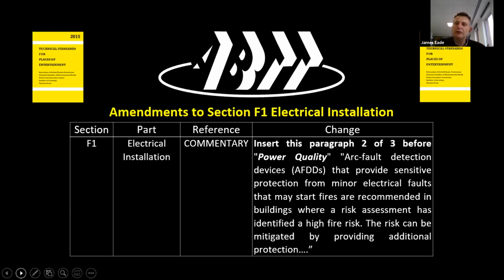But if the risk in a particular environment is low, like an event, for example, it's a managed system. Everyone's there while it's on, you turn it off when you go home at night. So if there are any latent faults that an AFDD would detect, they'll be detected anyway, because you'll see the cable smoking at the back of the stage, for example, during the show. So it's not unreasonable to take a pragmatic view on the implementation of such devices.